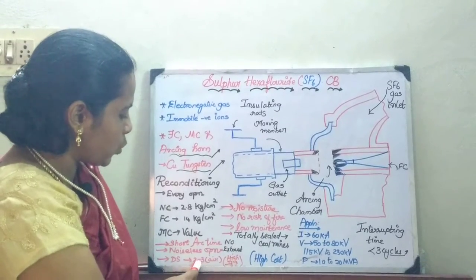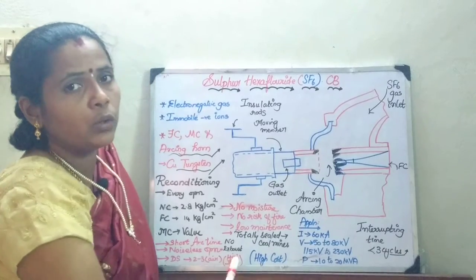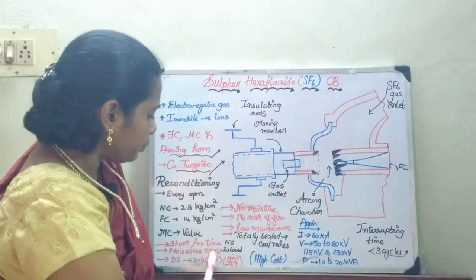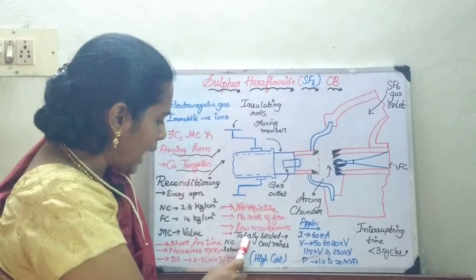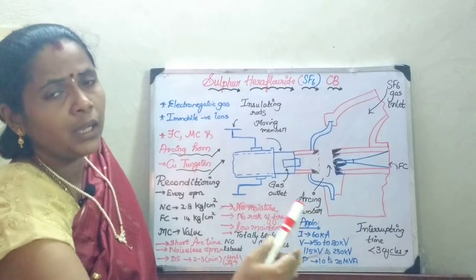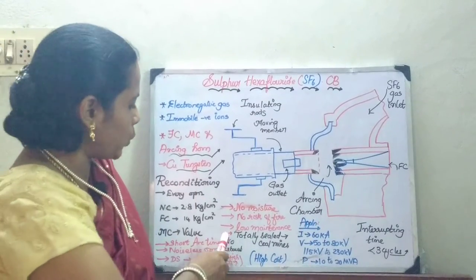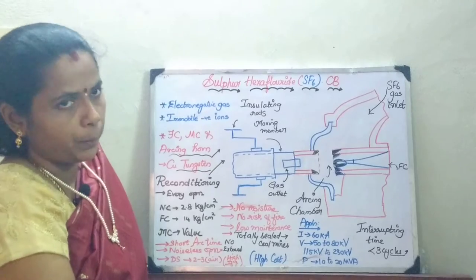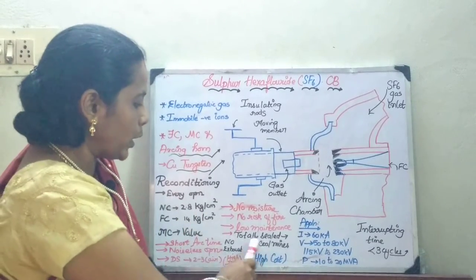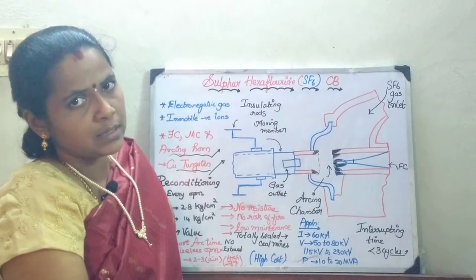The dielectric strength of SF6 is twice or thrice that of air, so arc interruption can be done for higher fault currents. Since it is a noiseless operation and no exhaust is fed into the atmosphere, this leads to a contamination-free operation. Since it is totally sealed, you can use it at coal mines.